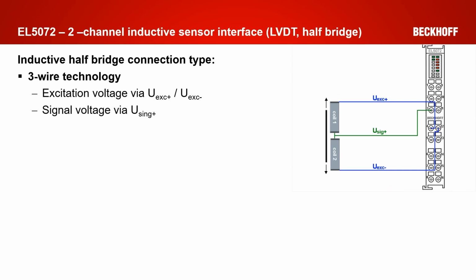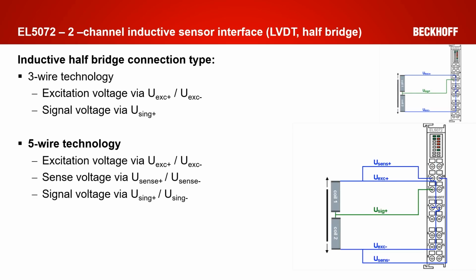For the connection of inductive half bridges, mostly the 3-wire technology is used. Here, the excitation voltage is fed in from the outside and the signal voltage is measured in between. We can also realize a ratiometric measurement by setting the excitation voltage and the measured voltage into ratio. By using an additional sense line, the excitation voltage can once more be measured currentless with a high impedance. So it is the same procedure as for the full bridge LVDT measurement. Also here, line-conditioned errors are avoided and we have a more accurate measurement.